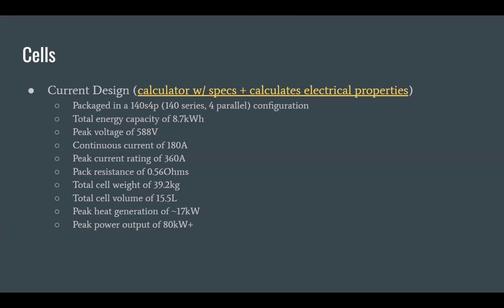One big thing I want to voice about this configuration is we kind of just said we want to get a maximum voltage that is as high as possible. We went with the idea that if you can output 180 amps at 600 volts, or 360 amps at 300 volts, you're always going to have better efficiency by going to higher voltages. That's why power lines use monstrously high voltages and AC.